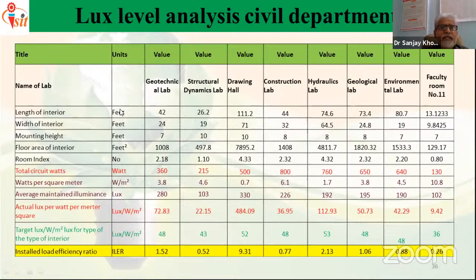Suppose I take one section, the geotechnical lab. Here we take all the dimensions - length, width, mounting height, where the tube lights are fitted - so the floor area is automatically obtained. Now, room index - there is a standard based on length, width, and height - we calculate the room index, which gives an idea of how many points we need to measure the lux level.